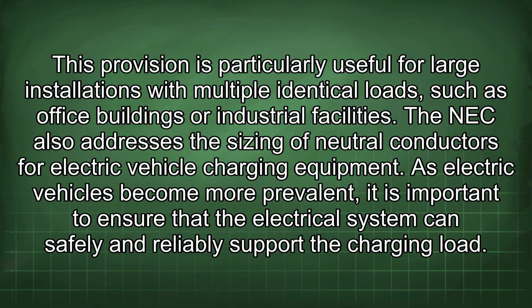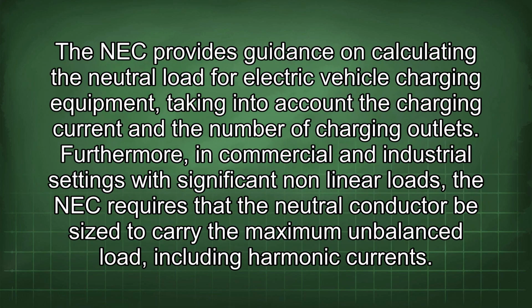The NEC also addresses the sizing of neutral conductors for electric vehicle charging equipment. As electric vehicles become more prevalent, it is important to ensure that the electrical system can safely and reliably support the charging load. The NEC provides guidance on calculating the neutral load for electric vehicle charging equipment, taking into account the charging current and the number of charging outlets.